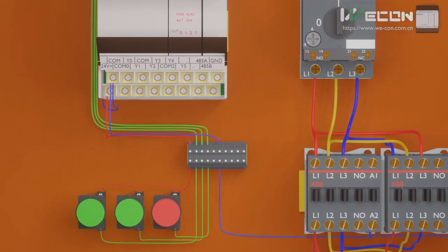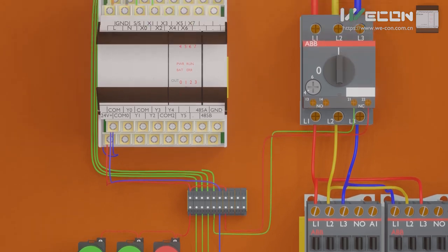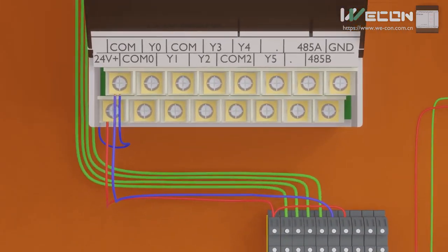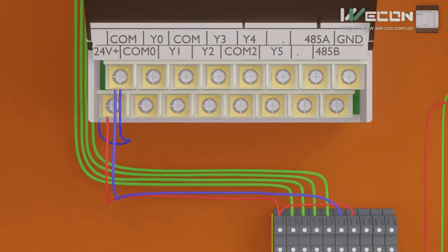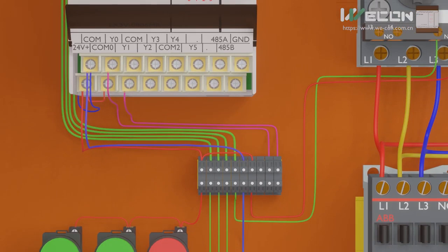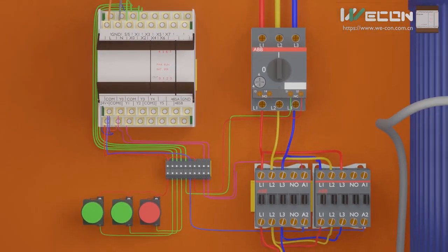Next, we take a wire from the positive terminal and connect it to the normally closed auxiliary contact of the motor protector, connecting this auxiliary contact at the X3 input terminal of the PLC. For the contactors, we connect 24V DC to the common zero terminal of the PLC — the common terminal for outputs Y0 and Y1 — and then connect outputs Y0 and Y1 to the A1 terminals of both contactors respectively.